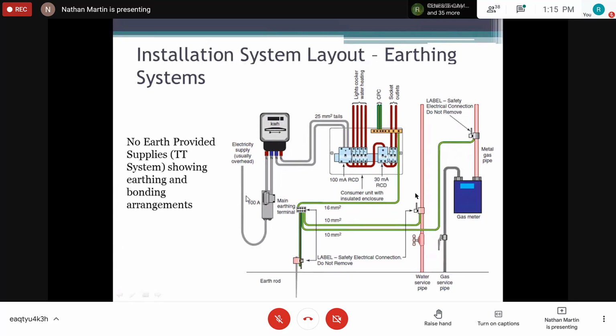On the JPS side, they would have earth and bond their earth to their neutral to keep their neutral at zero potential, but they don't supply an earth to us, right? So what we are getting is a live conductor and an earthed neutral conductor, but we have to provide our own local earthing system. So in case the company loses their neutral earth protection, then we are also protected at the consumer residence.